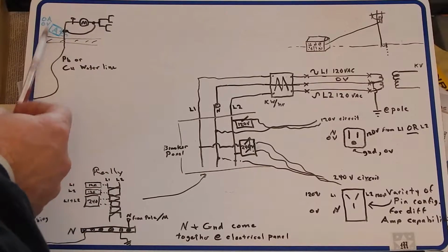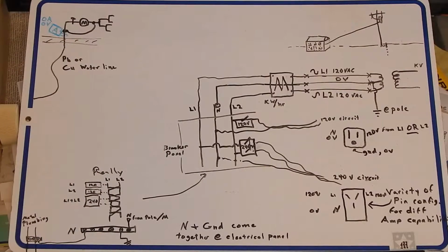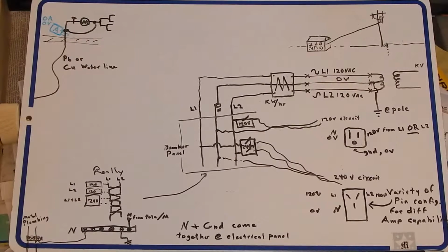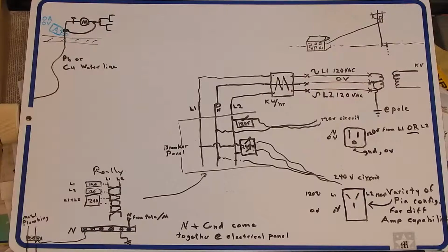If you did put a clamp amp meter here, and you watched it for a while, you'd want to watch it while different appliances are turning on and off in the house. If you started seeing major amperages, you know, 10, 20 amps going down that line, then you've definitely got a problem. And it's being camouflaged by your plumbing being such a good ground. Usually the plumbing isn't that great a ground, and you start to see the lights going bright dim in the house severely. Some outlets will have more voltage than 120, some outlets will have less than 120 volts on them. It wouldn't get to 240, only in an extreme theoretical case.